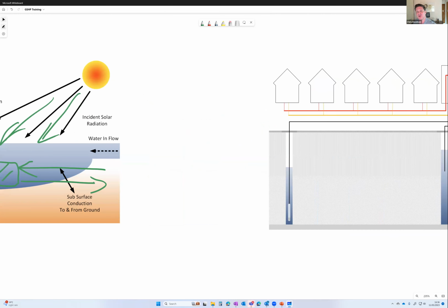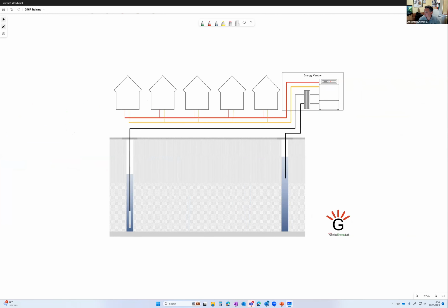Great questions. So there's another type of loop, which is open loop. In open loop, what we're doing is taking water from a body of water — I've shown it here as an underground aquifer. We take it out of the ground, warm it up or cool it down, and put it back into the ground again. Over time that water will propagate between the 2 boreholes. So it is a loop, but it's got an open element to it. This is a different animal really from closed loop. In closed loop, what's inside the loop we've put there and we know exactly what that is. Here we're dealing with water that's open to the environment, so we've got water quality to consider.